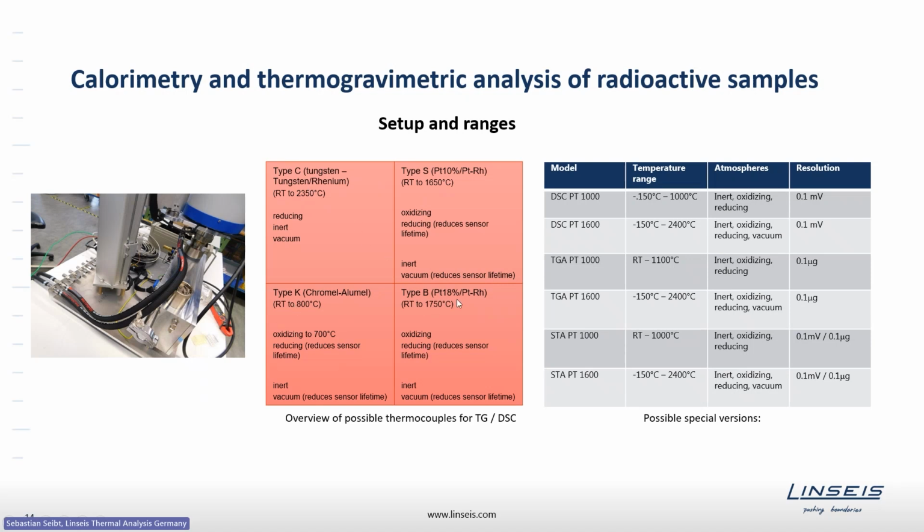These thermocouples are all meant for different atmospheres. It depends a little bit on the atmosphere you want to use and the temperature range you want to use. So out of atmosphere and temperature range combination, you can select the proper thermocouple or thermosensor for your sensor head.